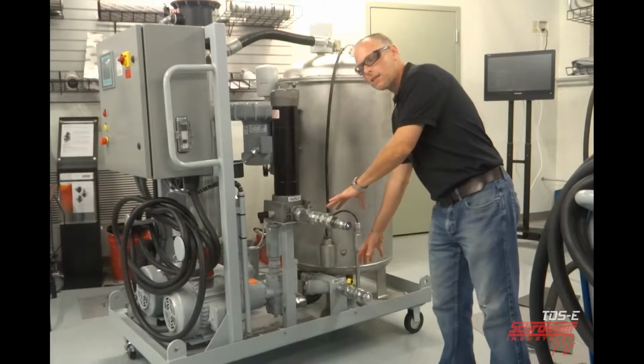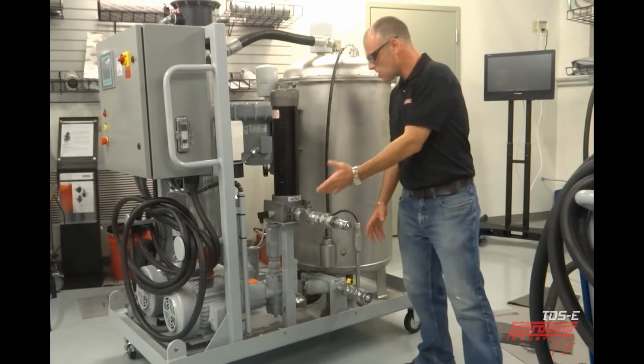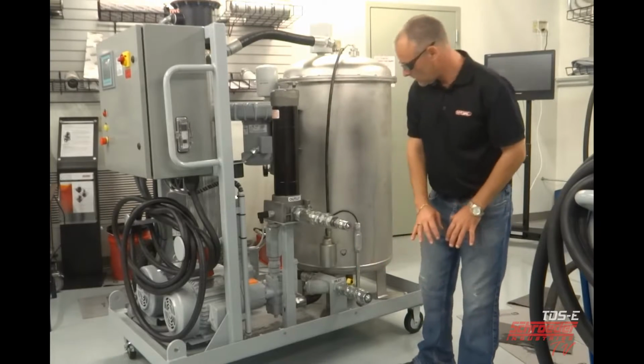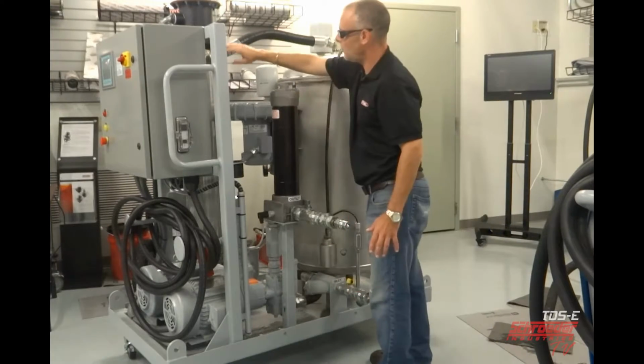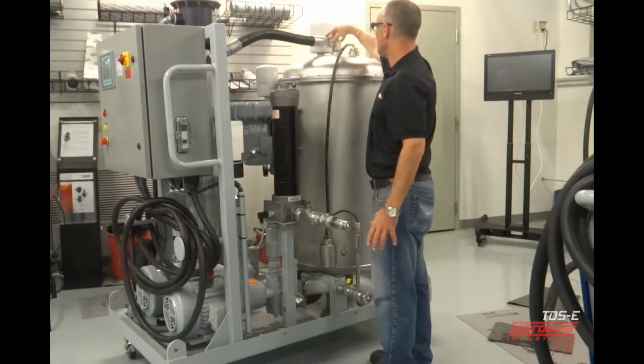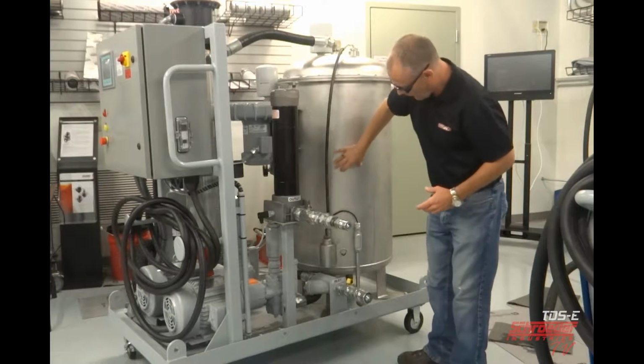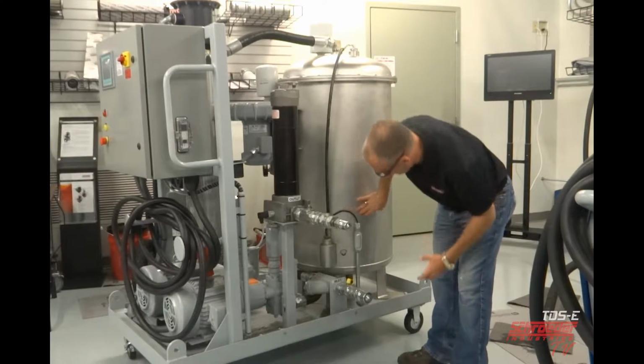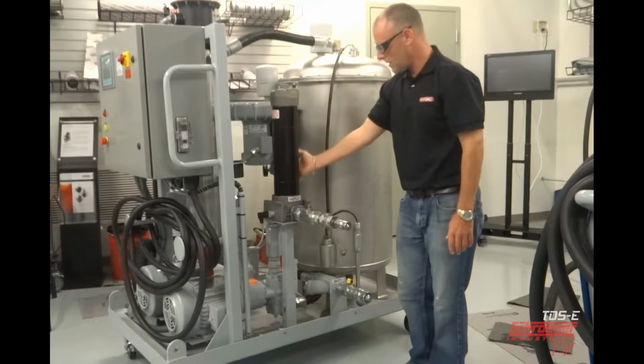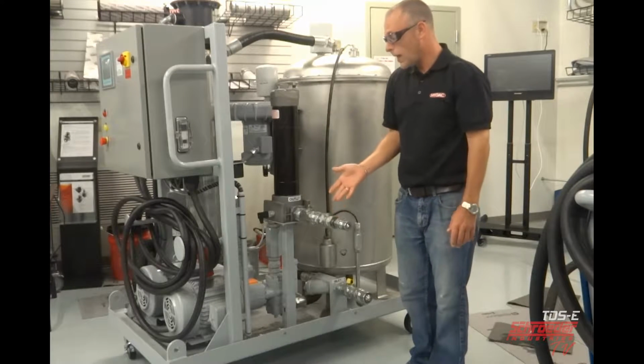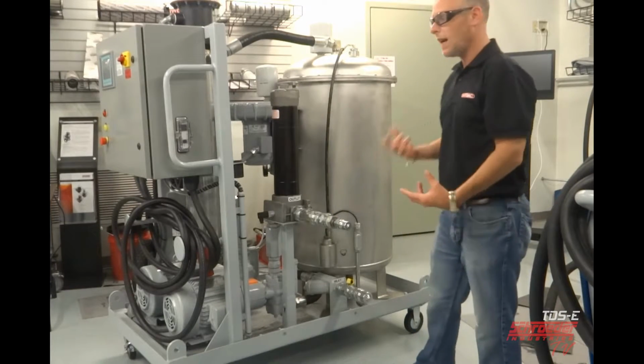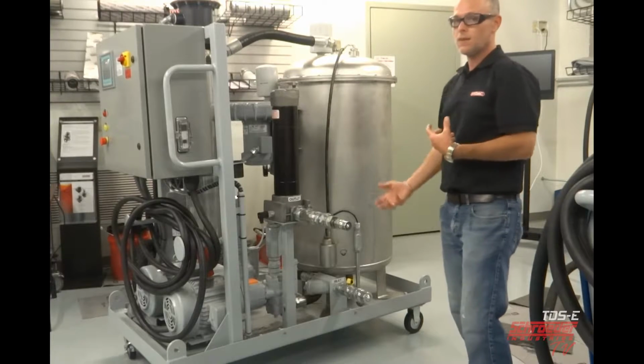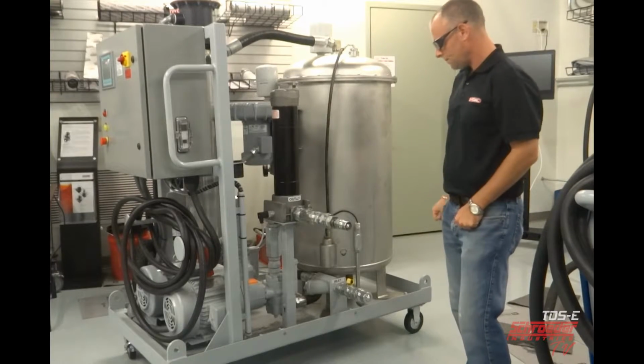The system fluid is cycled through the reaction chamber in between two level switches. During the first cycle, fluid is pumped and gently sprayed on top of the loose reticulated media until the fluid level in the sump triggers the high float switch. The fluid is then pumped from the sump and returned to the customer's reservoir. After the initial cycle, the spray and drain pumps are synchronized to continuously pump fluid in both directions.